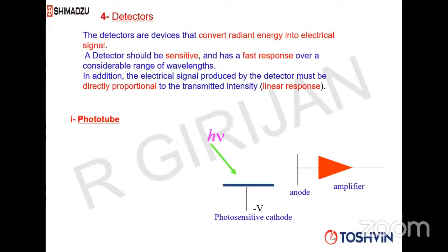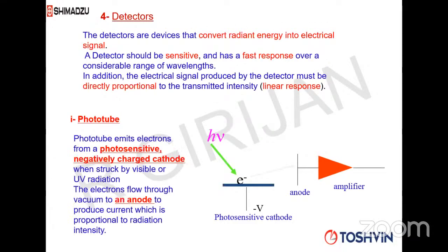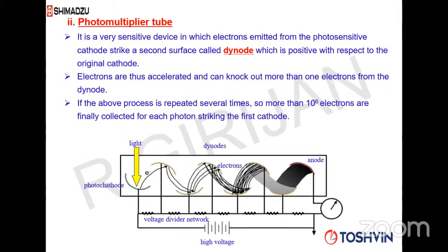Okay. And coming to detector, of course, this electronics part, we have different detectors available in UV. PMT, the photomultiplier tube, is the most powerful one. Then we have got silicon photodiode. Then we have got indium gallium arsenide for NIR region. So different detectors are available. PMT is supposed to be the most powerful detector, and the PMT is also costly. So some of the high-end models we are putting PMT. These are basically electronic parts, I am not going into how the photomultiplier tube functions.